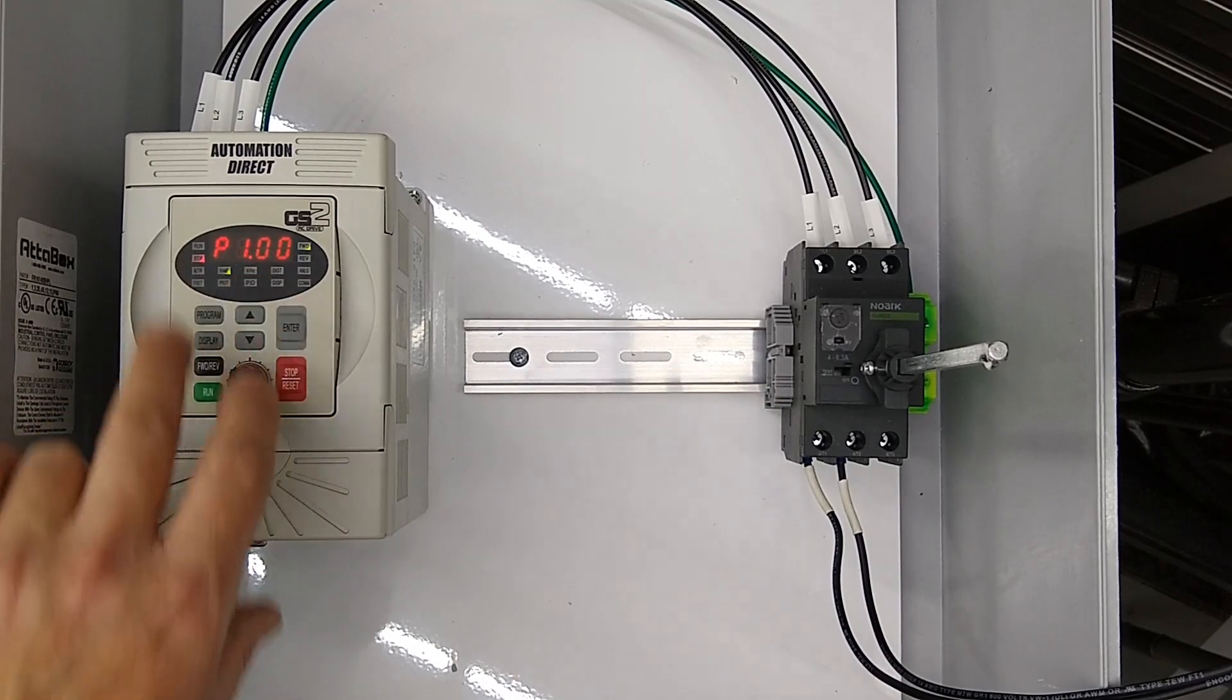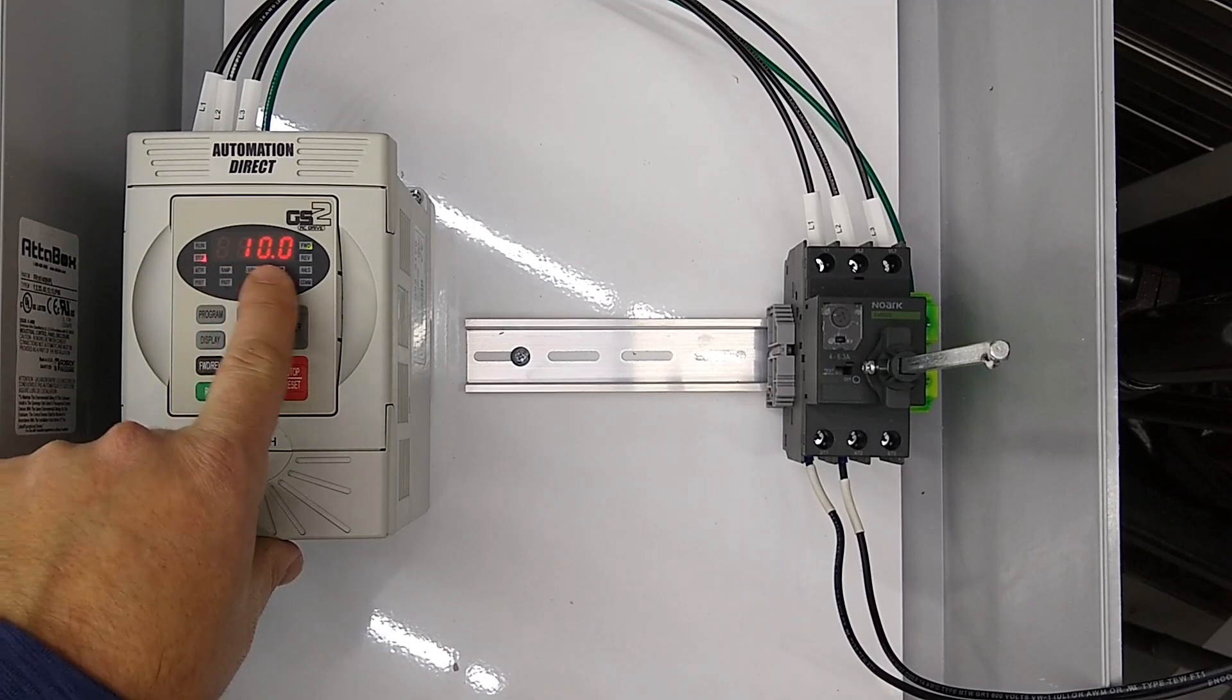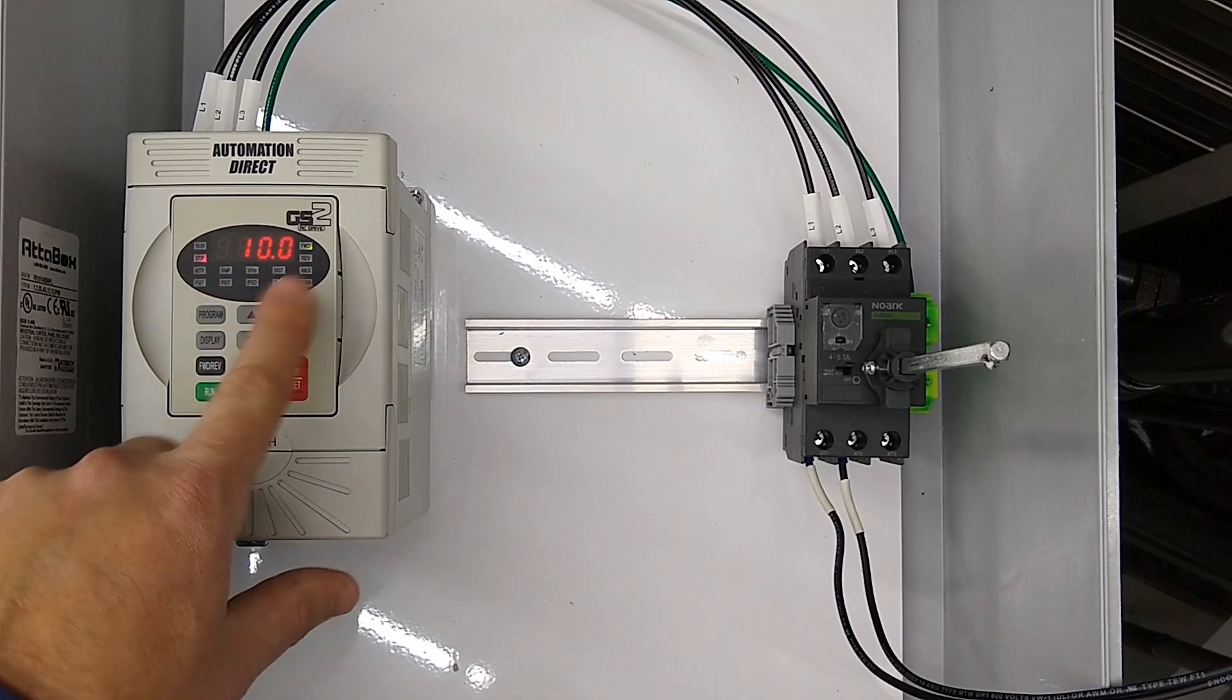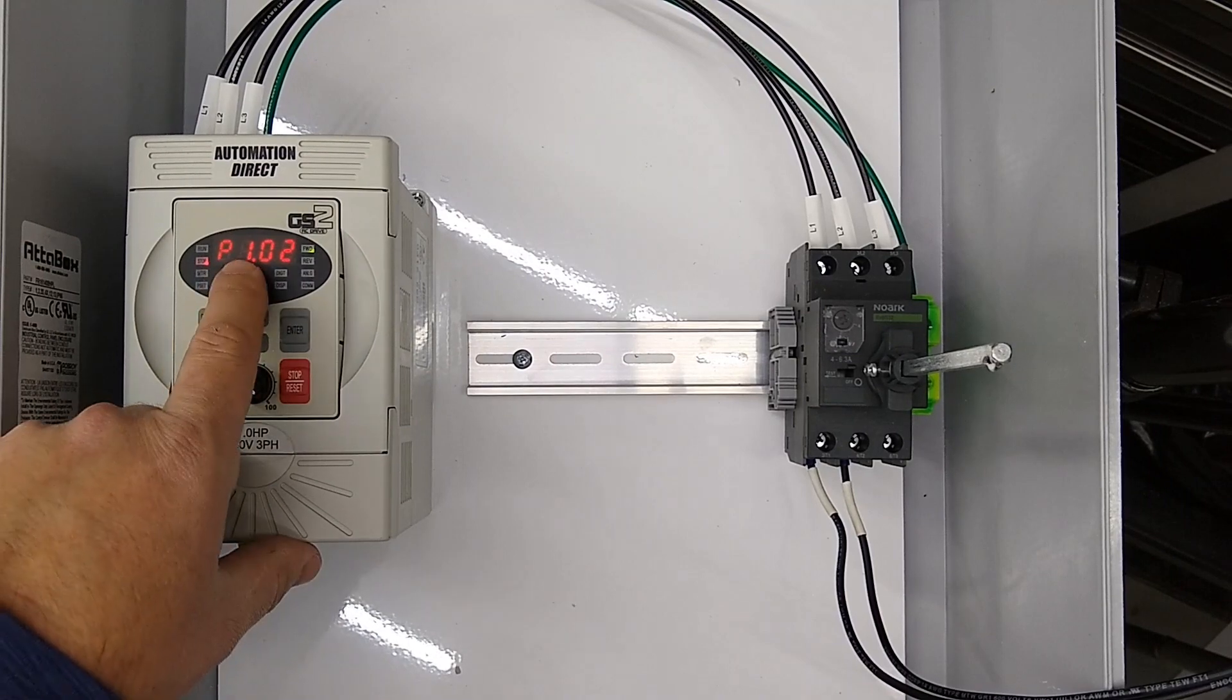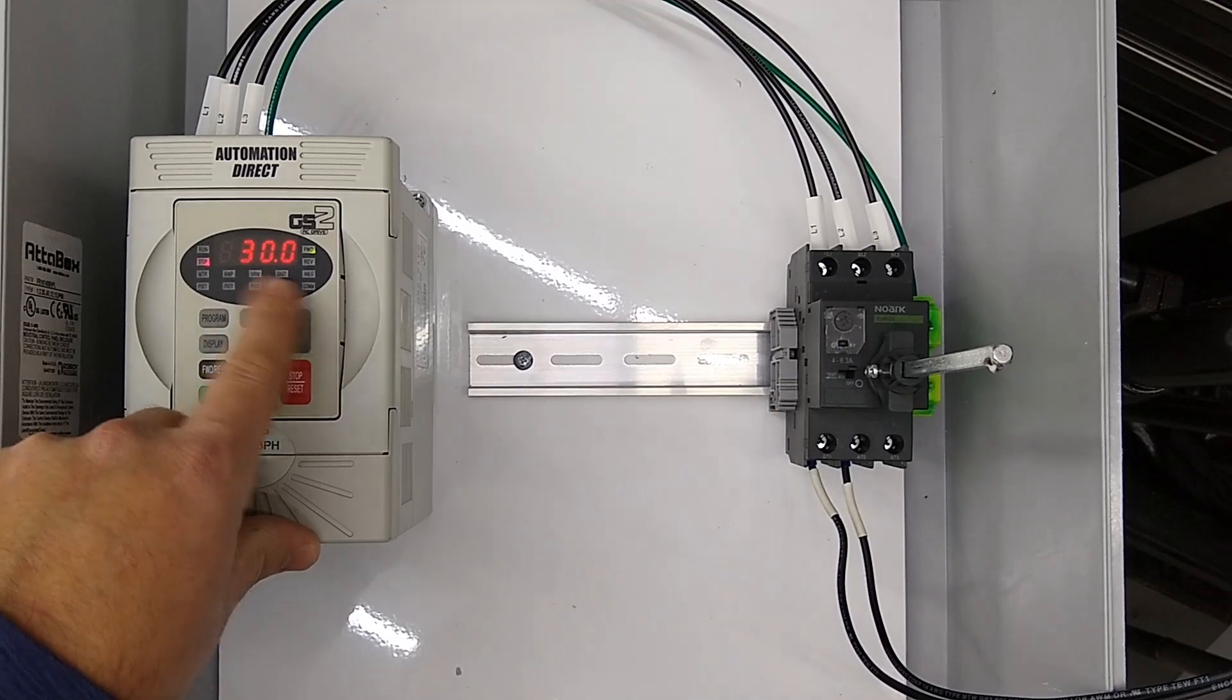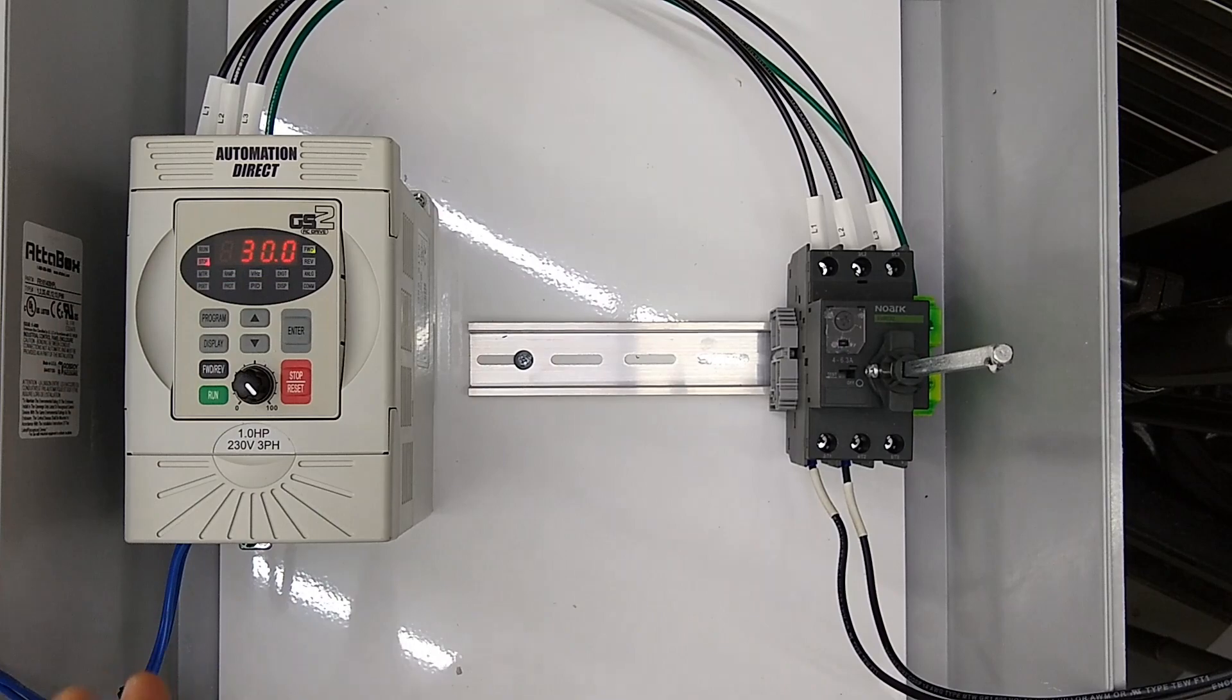Then p01, that's going to be your acceleration time. So right now it's accelerating from zero to full speed in 10 seconds—that's probably a little high, but you'll adjust it to what you want. Then you have your decel time, which is p1.02, and right now it's at 30. I've never found an application that needs 30 seconds, so you'll probably want to bring this way down. But those are the settings that you'll mainly need to know.